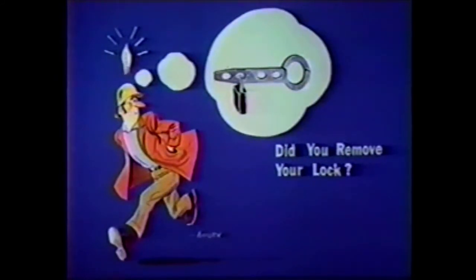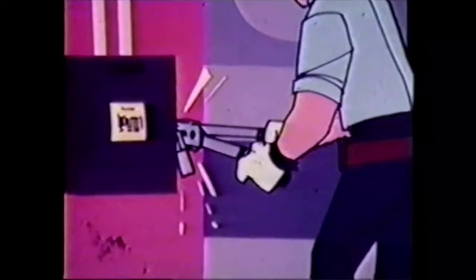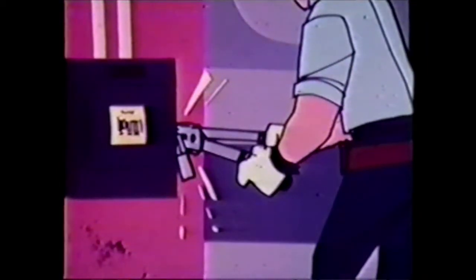Under normal circumstances, a lock should be removed only by the authorized employee to whom the lock is assigned. In an emergency, someone else's lock can be removed only after procedures are established for emergency lock removal. The procedures would involve the approval of management to ensure the safety of all personnel and locating the missing authorized person. The plant manager or designated person shall be responsible for cutting the lock. The missing person must have knowledge of the removed lock before resuming work.